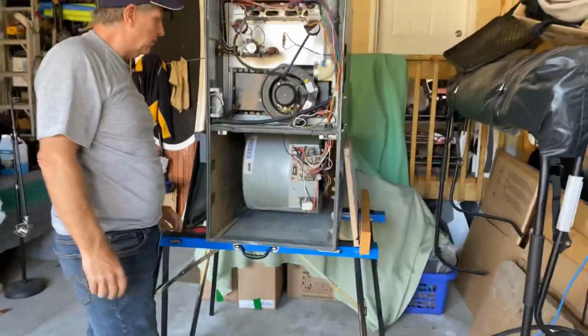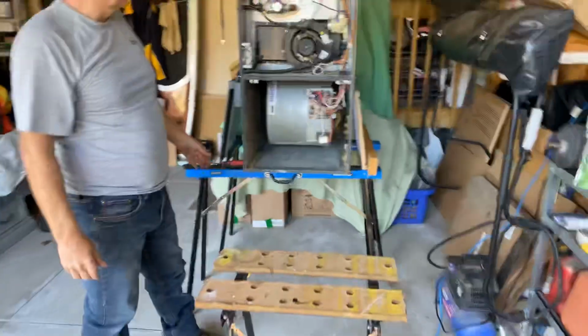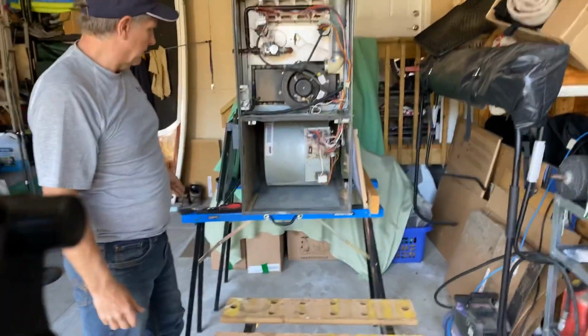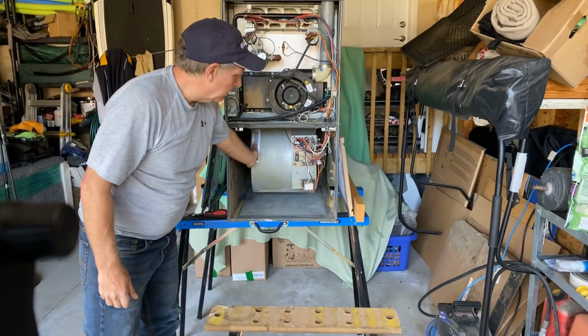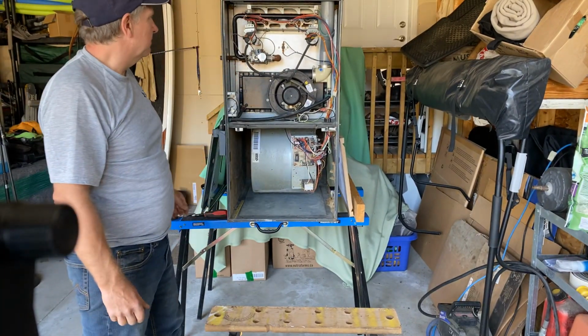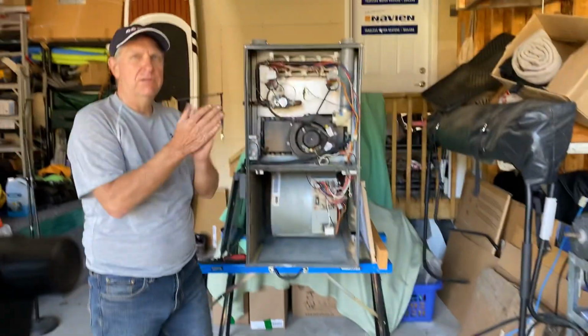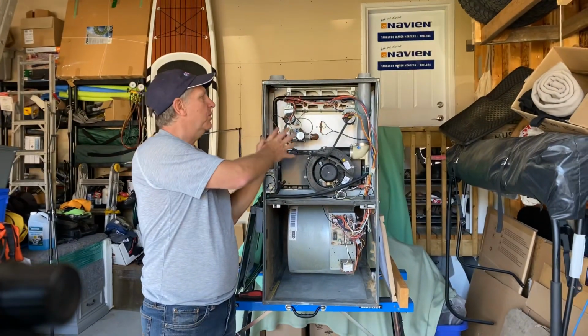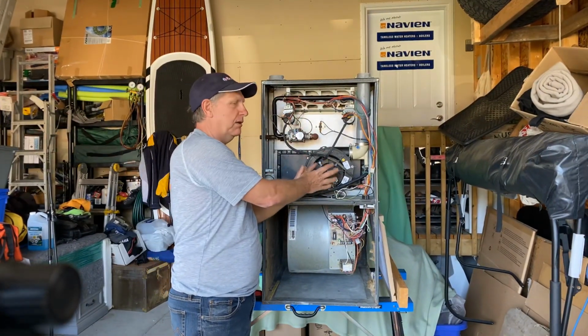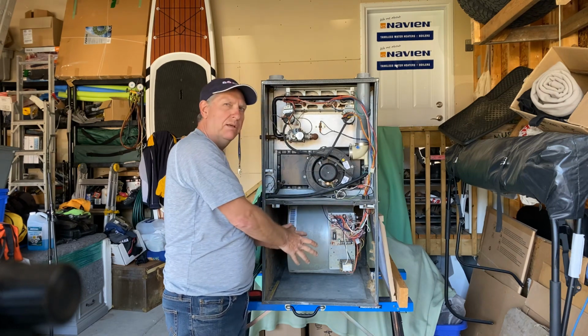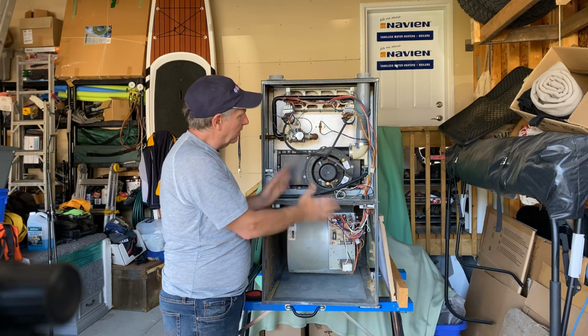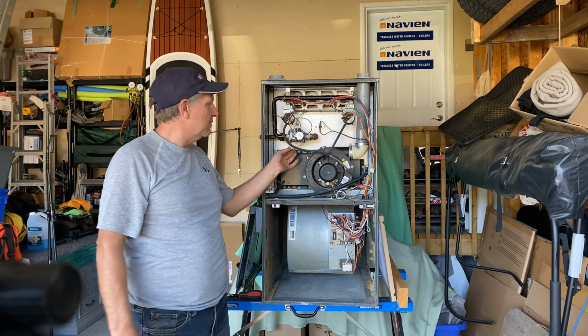We're good to go. So that's blower removed, blower replaced, all good to go. I think that's pretty much everything. So there we go: service, removing and replacing the burner, removing and replacing the induced draft motor, removing and replacing the blower, and looking at a few of the other components.